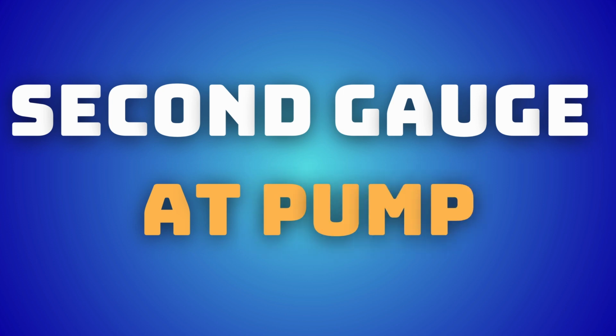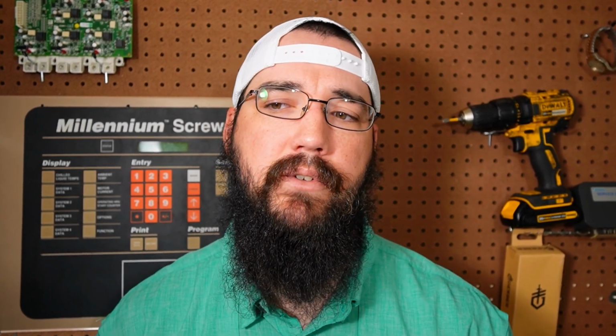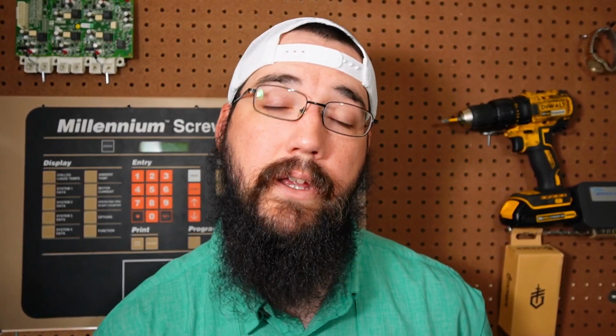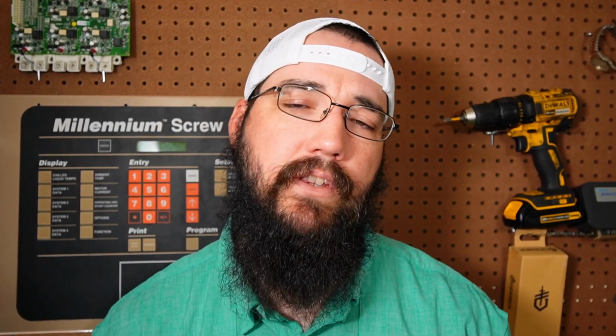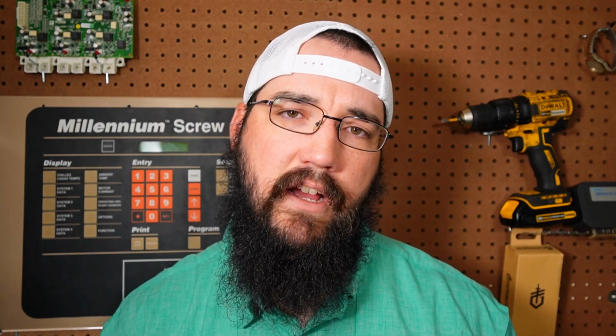This isn't necessarily special. A practice I like using when I can is having a second gauge. What I did initially is I took my old busted gauge that I didn't really trust all that much, but it was kind of sort of accurate enough. Then I put that gauge at my pump. Its sole purpose wasn't necessarily to have an accurate reading, but to be an indicator of how well the pump was still doing and what the pump oil was doing. Obviously the gauge still functions in some way, but when I see that gauge at the pump begin to equalize to my actual system gauge on the piping, or when I see it stall out or start to rise at the pump, that tells me the pump itself, or more than likely the oil, needs to be changed.